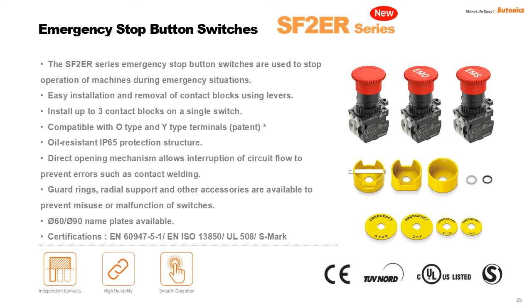The most important thing is our SF2ER series achieves the international standard EN 60947-5-1. It is a direct opening mechanism design. So everybody will ask, what is the purpose of a direct opening mechanism? For your information, during some operations, the contact points can stick together. So this mechanical design can ensure that after we press down the emergency stop switch, the contact points will totally release and achieve the OSSD off function.